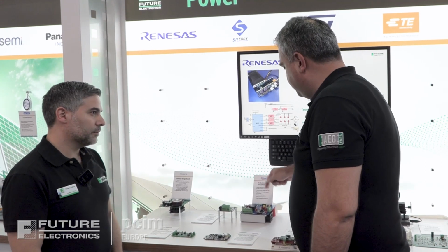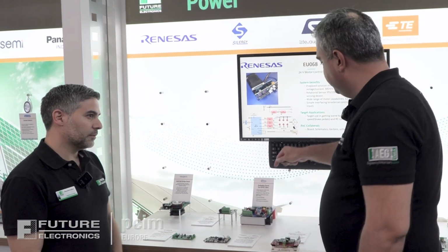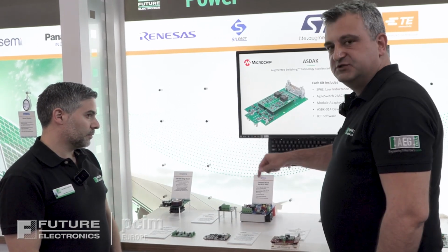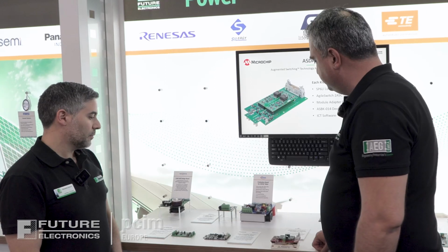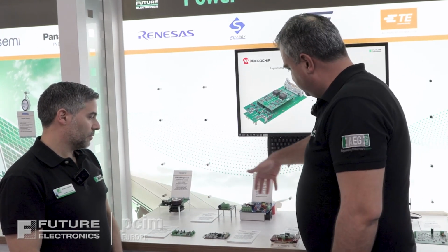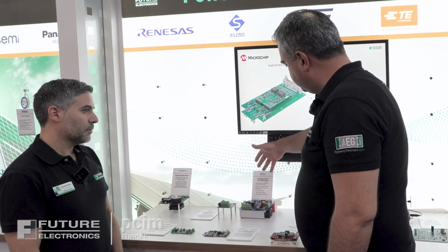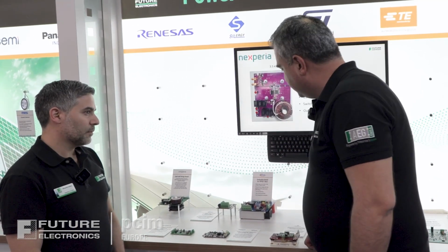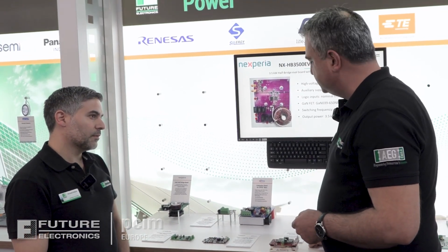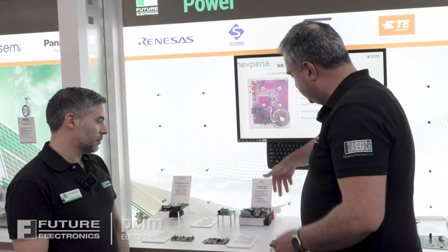It's a silicon carbide IPM with 3 half bridge stages integrated. But the gate driver is also integrated in the bootstrap configuration. It can be used in motor drive applications. In this case, it can drive up to an 8 kilowatt motor. Inside this IPM, there are 1200 volt silicon carbide MOSFETs with 55 milliohm RDS(on), and the efficiency for the inverter stage can go up to 99%.